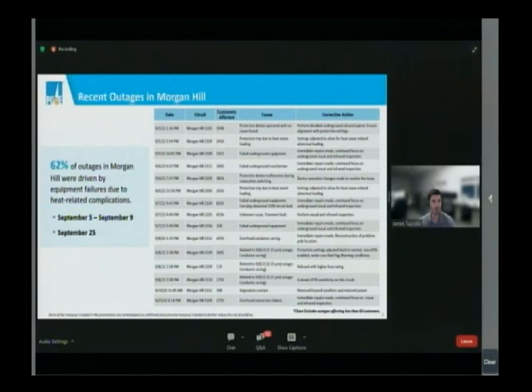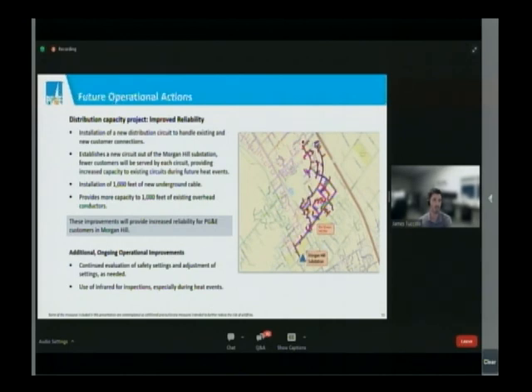The first outage there on the top, that was the 3:54 p.m. on 9/5, again, was related to the sensitivity of our settings on that line recloser, that protective device that I had showed kind of in the middle of the screen. And it needs to be set sensitive enough to protect against the fire risk, while also having enough margin to accommodate what we projected was the peak load to be expected on that device. So during the heat event, the peak load grew beyond what we had expected due to the duration and the amount of load, and ended up operating the device. That was the first outage there at 3:54 p.m. on 9/5. Subsequent outage that same evening, again, we resolved that issue. We got that device back in service. And then after the circuit was re-energized, unfortunately, we had another outage as a result of the equipment failure.